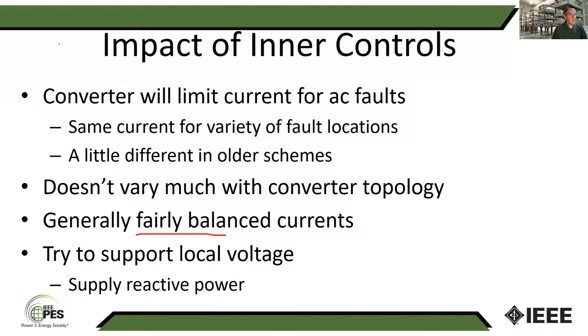In some cases, we also are seeing more of them being controlled to be able to support local voltage. So the original version of IEEE 1547 did not allow converters for distributed generation to regulate voltage. They had to operate at a fixed power factor. They could operate at unity power factor, they could operate at a power factor where they're supplying reactive power or one where they're consuming reactive power. One of the other things that came with the discussions of IEEE 1547 was getting away from the idea of saying leading power factor versus lagging power factor, because it starts to get to be confusing if you look at some case where you have metering where the power could go out for a while and then go the other direction for a while. How do you define that?